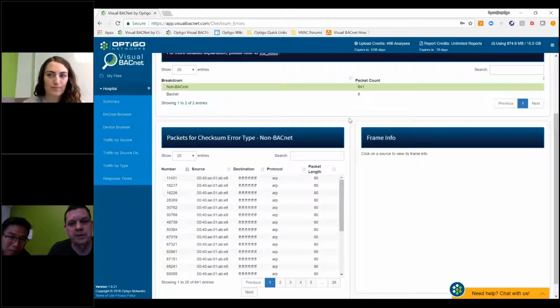Sometimes it could be the sign of a loose connection. And this is always coming from the same source. Right, it's all coming from the exact same location. So it might be an idea. It's obviously broadcasting out, but it could be an indication of something happening on the site. You could either go and try and re-terminate the connections, or just keep an eye on it to see if it gets worse.